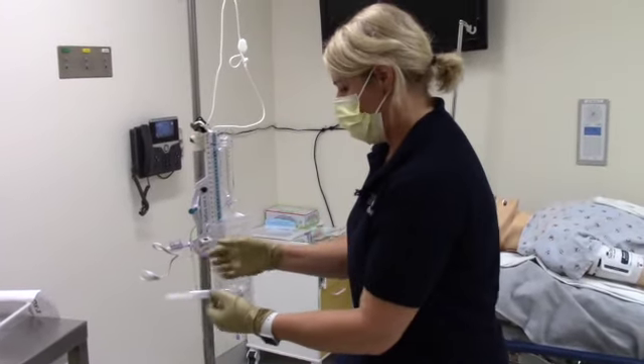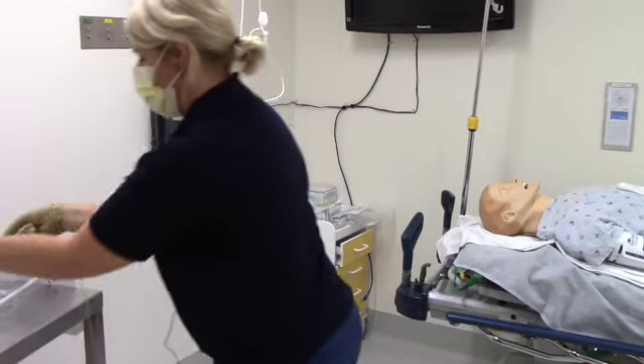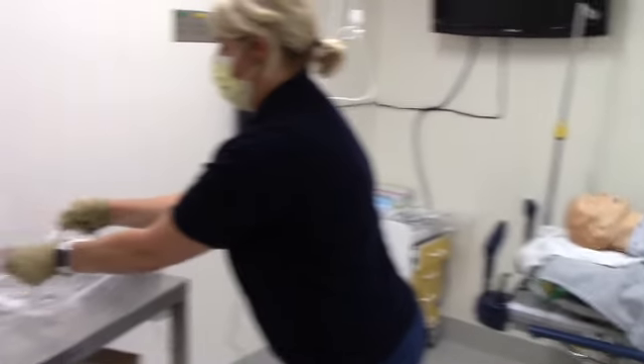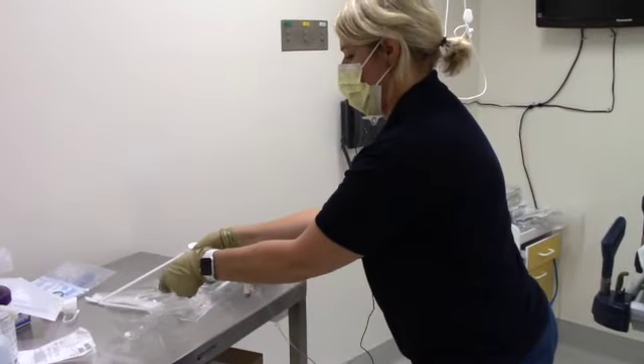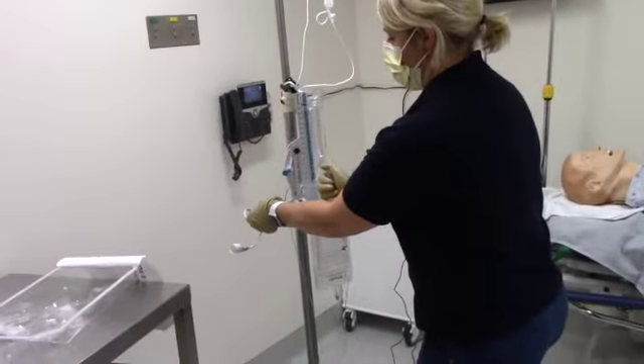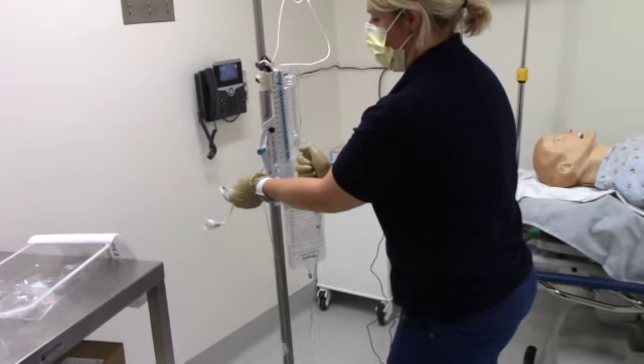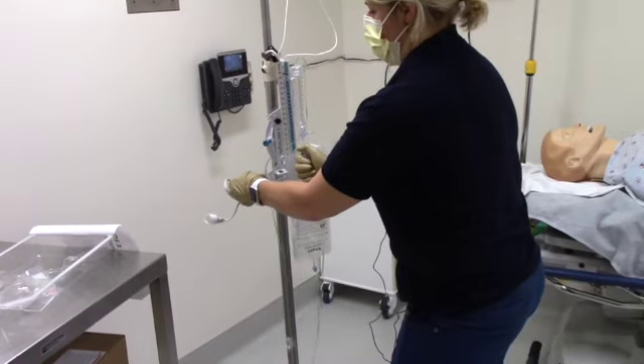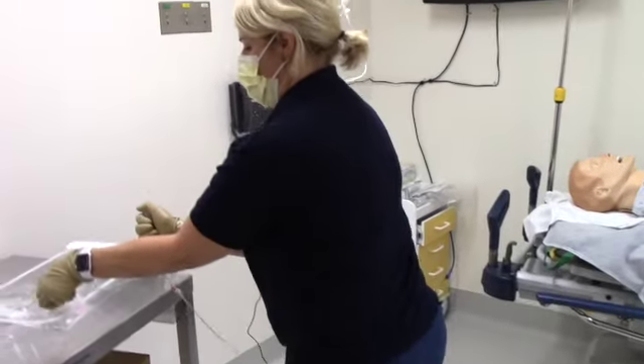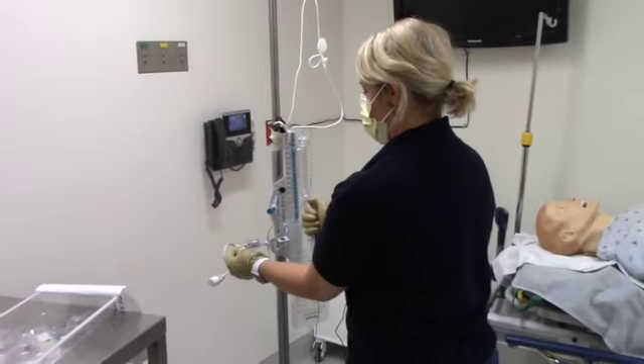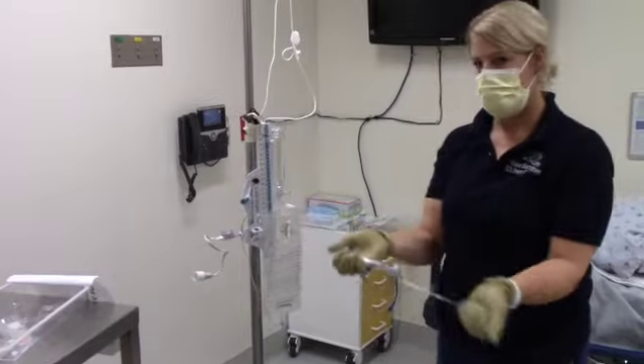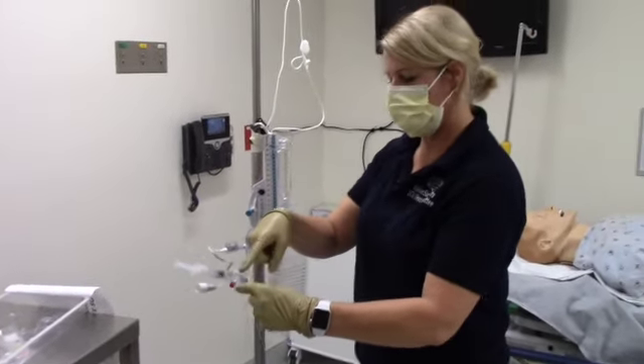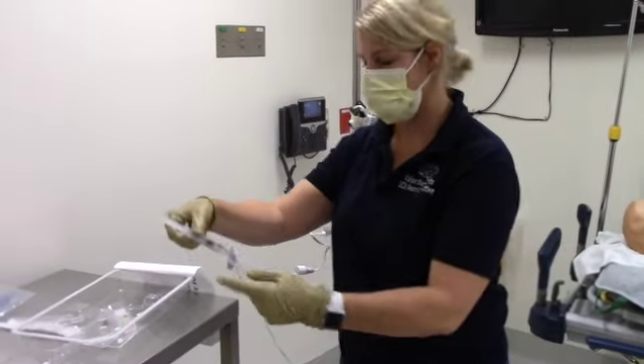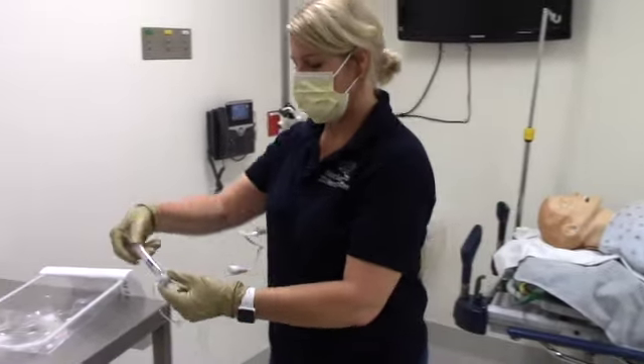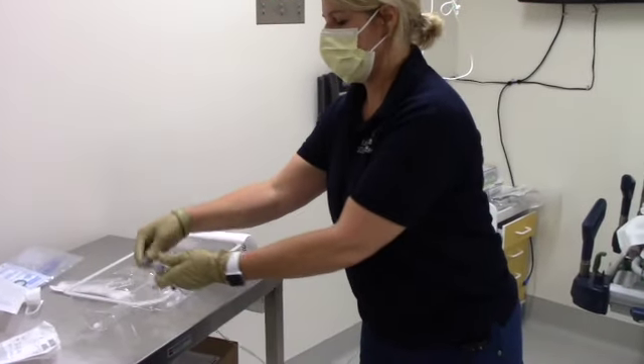So next step is we're going to flush out the transducer and replace it with one of these closed end caps. So I usually remove, as I'm flushing, I remove the cap and replace it at the same time. And there we go. Last step is to replace the last white rimmed hub with the syringe. And again, we're not turning any stopcocks so that we won't lose any, we won't suck back any fluid. The last white rimmed hub goes there.